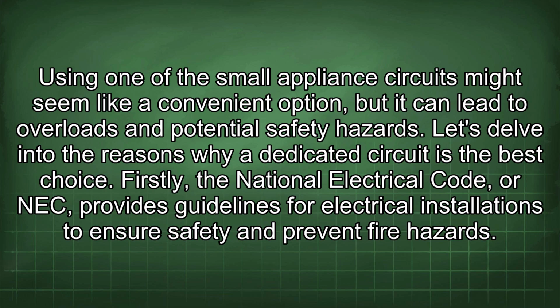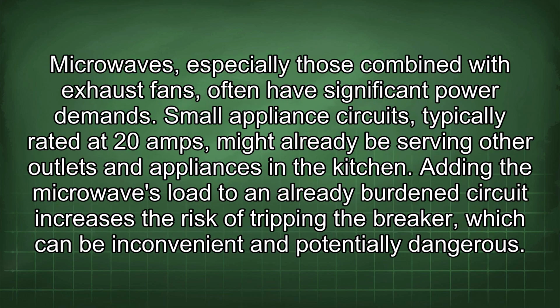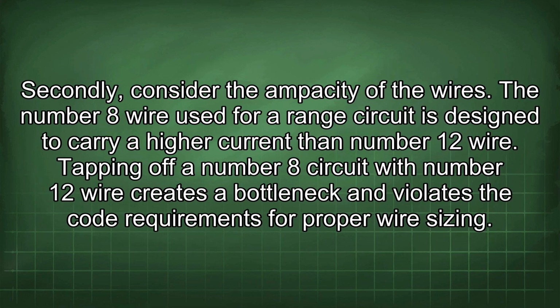Firstly, the National Electrical Code, or NEC, provides guidelines for electrical installations to ensure safety and prevent fire hazards. Microwaves, especially those combined with exhaust fans, often have significant power demands. Small appliance circuits, typically rated at 20 amps, might already be serving other outlets and appliances in the kitchen. Adding the microwave's load to an already burdened circuit increases the risk of tripping the breaker, which can be inconvenient and potentially dangerous. Secondly, consider the ampacity of the wires.